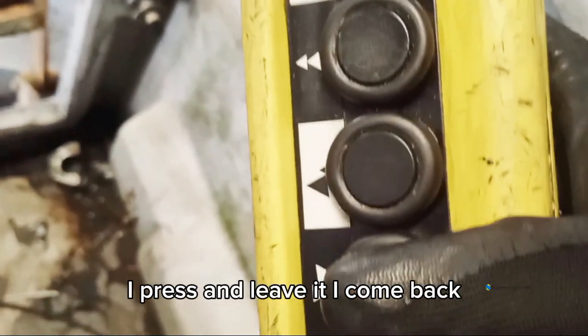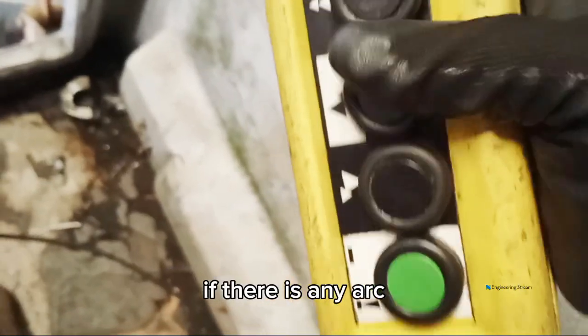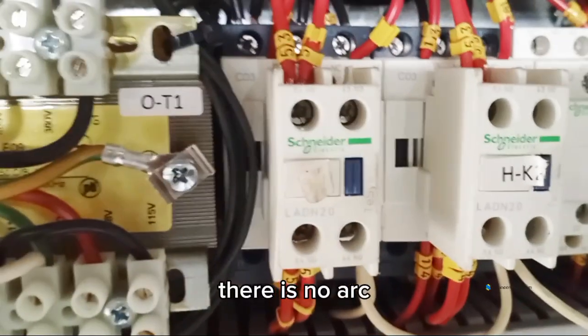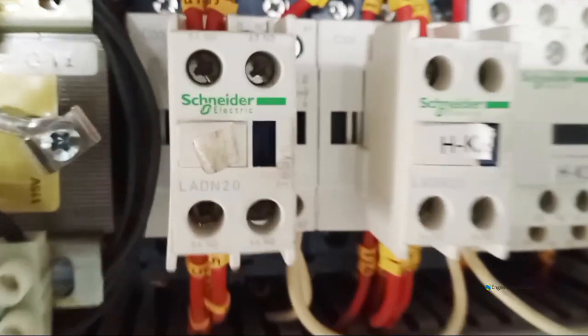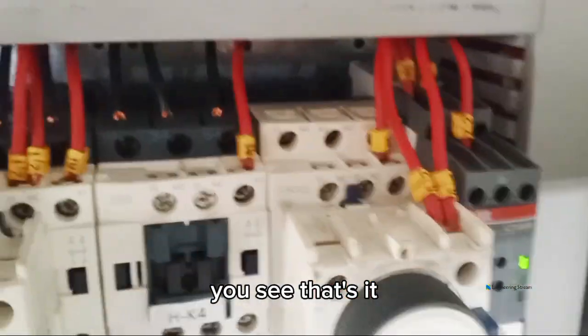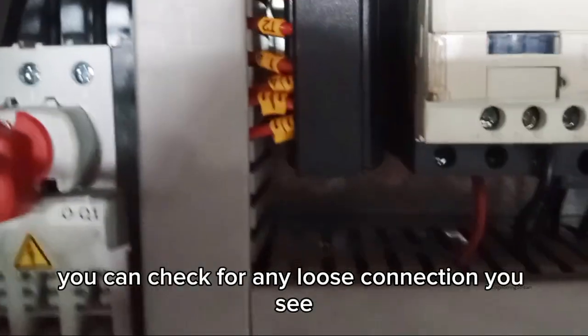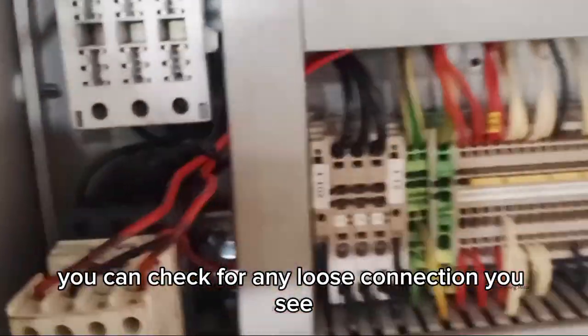Now if I want to detect that, I just press and release intermittently. This is the button, crane travel drive. I press and leave it. I come back, I press and leave it, and I observe the contact if there is any arc. Watch me. You see? There is no arc. I come back. No arc. You see? That's the off delay timer that is on. This is how you check for any loose connection. This is another professional way you can check for any loose connection.